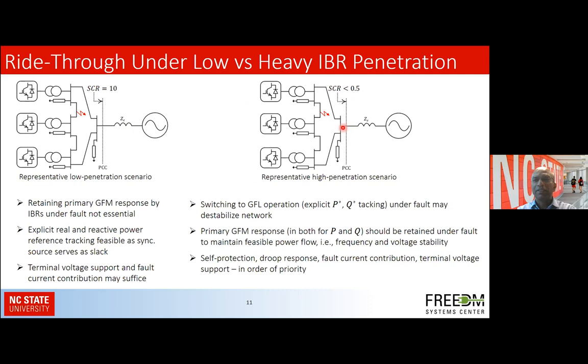And instead of increasing the strength of this interconnection by putting in more transmission capacity. So in the strong grid case, retaining the primary GFM response by the IBRs is not really essential. It can provide the terminal support and fault current contribution, and that would be enough. And if the interconnection strength is weak, then the common approach has been to switch to GFL operation under fault, and that would cause PLL issues, and that may destabilize the network. So retaining the primary GFM response under faults is of critical importance to maintain the feasible power flow, which means maintaining the frequency and the voltage stability.